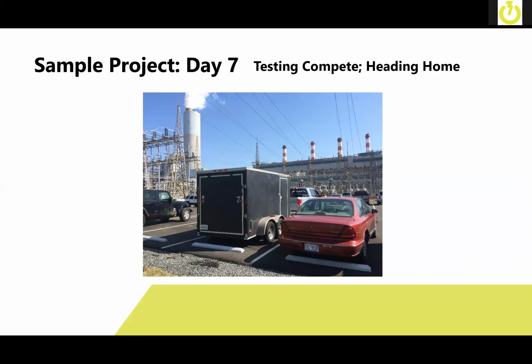After we did the relay retrofit, we took day 6 and part of day 7, and we basically went through and we pushed all current sensing. We basically pushed current through the entire system. We injected voltage throughout the system. We tripped every device. We rolled every lockout, made sure that all the inputs were getting the proper signals from the customer's equipment, and went through the full testing regimen. And by the end of day 7, we basically had the trailer fully packed up and we were ready to come home.